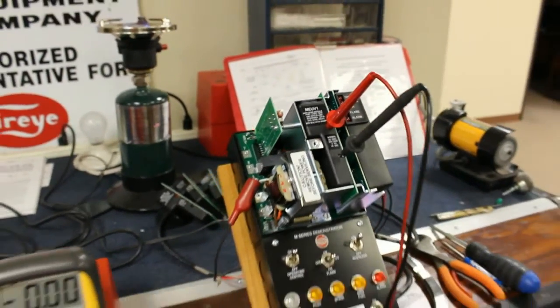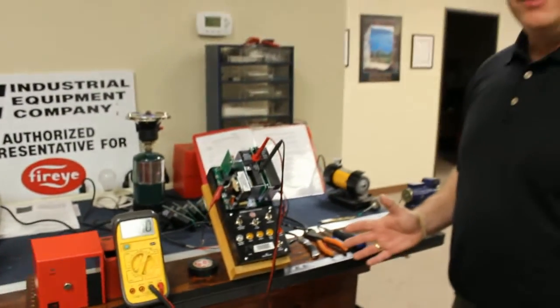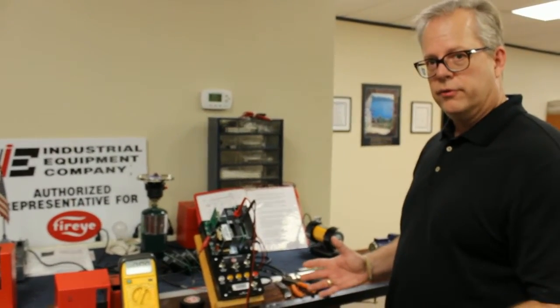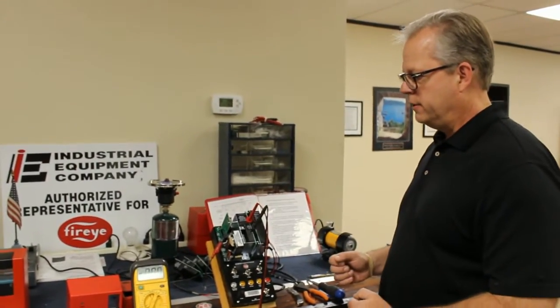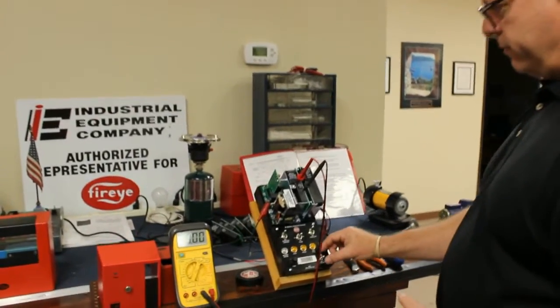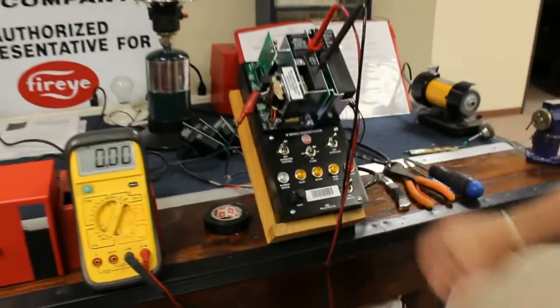So the key to diagnosing a Fireye is understanding at what point in the sequence we're failing at.